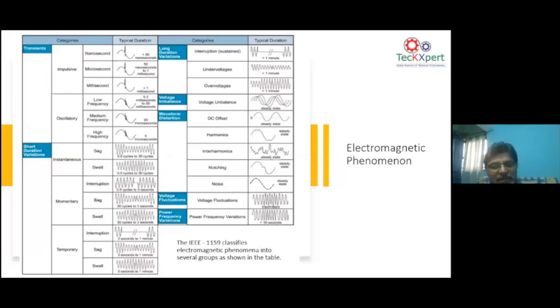A swell is a voltage increase. Let's say it goes up by 20% of rated voltage and remains for a few cycles, then we call it a swell. Interruption, as we are familiar with in India, could be a short interruption or a long interruption. Now, the long voltage variations are undervoltage and overvoltage. Undervoltage and overvoltage can last for minutes. You are seeing that transients and short durations are either in microseconds or a few cycles of waveforms, but overvoltage and undervoltage can be there for a few minutes. So that's why we call them long duration voltage variations.